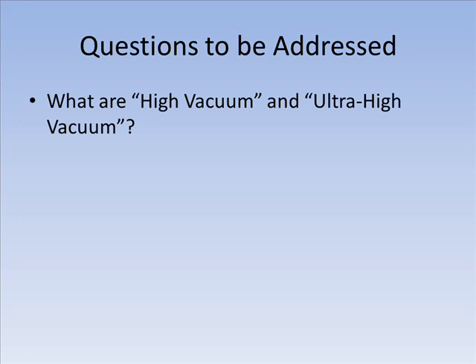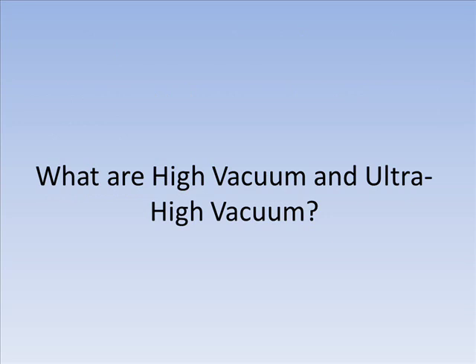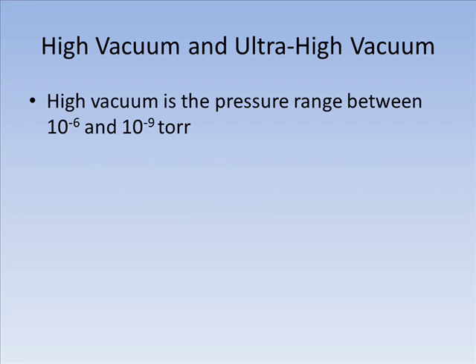We begin by addressing the questions: what do we mean by high and ultra-high vacuum, why are they useful, and how do we build vacuum systems? High and ultra-high vacuum are just terms for two different pressure regimes. High vacuum systems have a pressure that lies approximately within the range of 10 to the minus 6 to 10 to the minus 9 torr, but this range can vary widely depending on who you ask. Sometimes a distinction is made between high vacuum and very high vacuum, but when I refer to high vacuum, I will be referring to the range shown here.